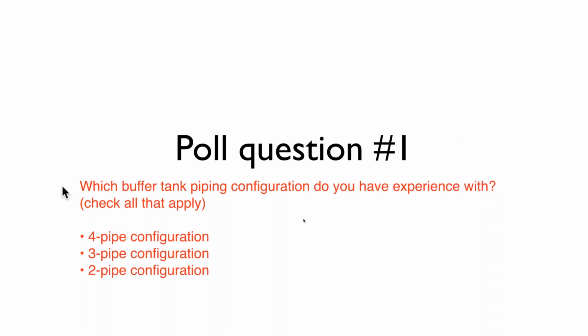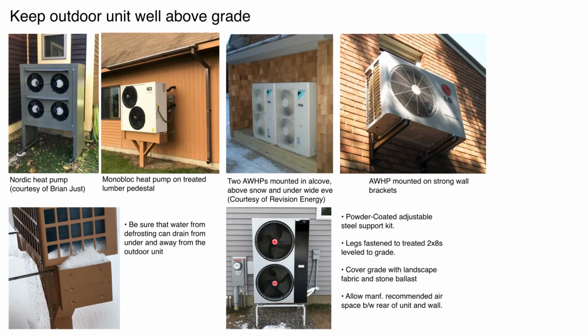Okay, so let's go on here. Outdoor details. Now here's several different types of air-to-water units. Most of these are monoblock. A couple of them are split systems. And the important thing here is, remember that we're going to use this in a winter. These are suitable for cold winter climates where we get a lot of snow. And we want to make sure that that heat pump is elevated up off the ground. And I'm going to suggest a minimum of a foot.